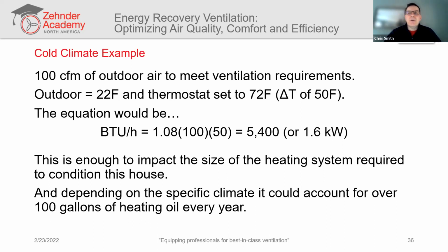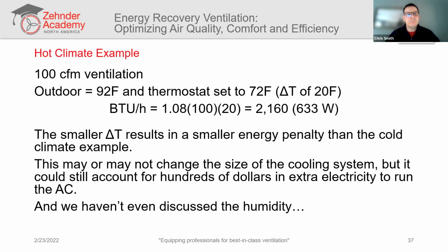And by the way, a 100 CFM ventilation rate is not an unusual ventilation rate for a residential building. And 5,400 BTUs per hour, or 1.6 kilowatts, is big enough to impact the size of the heating system required to condition the house. Depending on the climate you're in, if you're in a Vermont climate, for instance, this could account for over 100 gallons of heating oil every year. So it's significant.